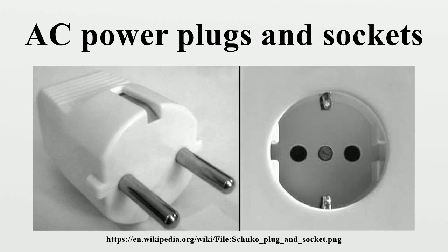2-pin sockets normally provide neutral and line connections, both of which carry current and are defined as live parts. Neutral is usually very near to earth potential, usually being earthed either at the distribution board or at the substation. Line carries the full supply voltage relative to the neutral. 3-pin sockets provide, in addition, a protective earth connection for exposed metal parts of an appliance. If internal insulation should fail, a short circuit to the earthed exposed metal parts will hold them at a low potential, and should operate fuses or circuit breakers to isolate the faulty appliance from the supply.